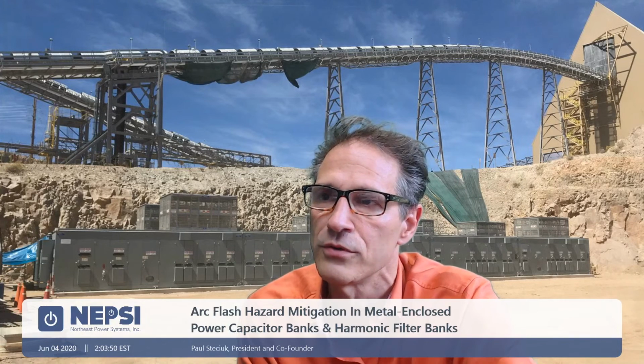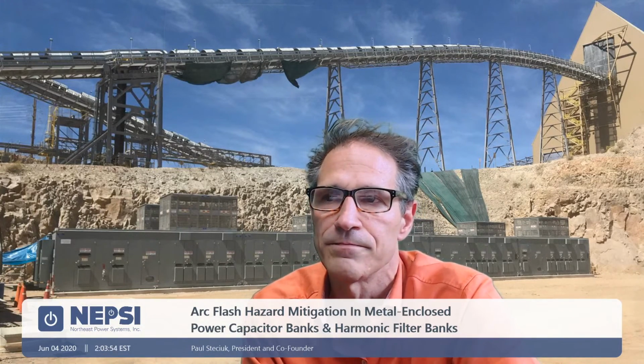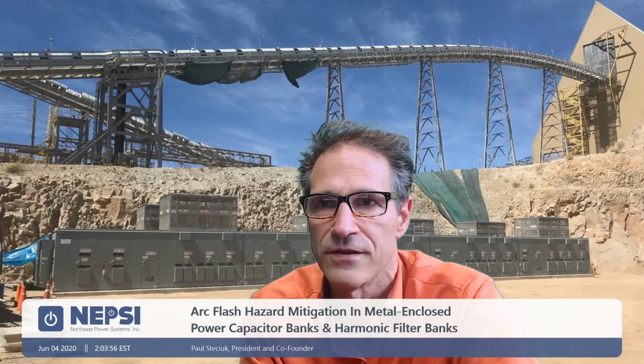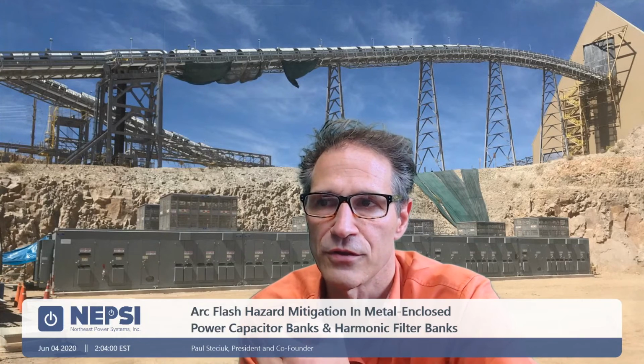This Toquepala mine site is a remote application on a relatively weak system. And if the filter system were to go out of service because of an internal arc flash event, it would put the equipment out of service. And because the filter was not able to operate, the mine would not be able to operate. It would cost millions of dollars a day. So when thinking about arc flash mitigation, it's not only about personnel safety, it's also about the equipment itself.